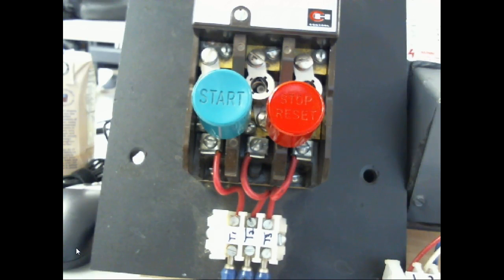So I've got L1 to L2 and L2 to L3. I've got a little note here that says don't forget this measurement. And then you'll disconnect all circuitry once I check your work. So we're going to deliberately single phase the motor so you can see what happens.